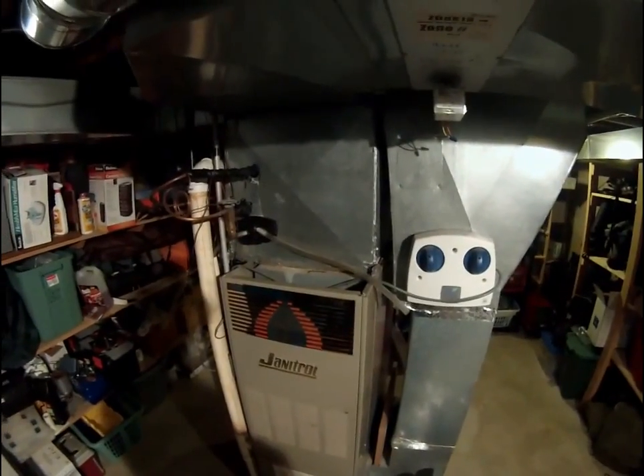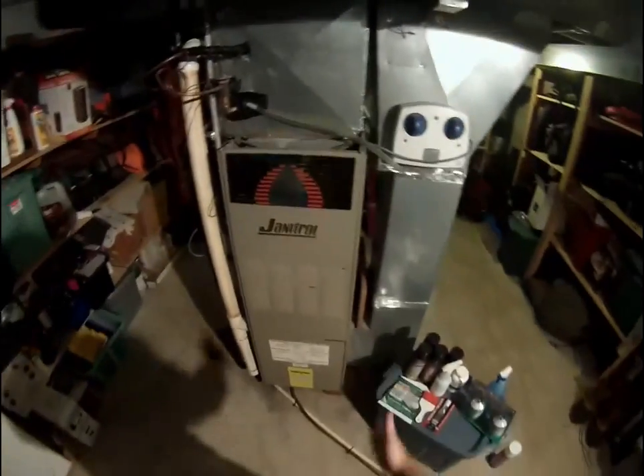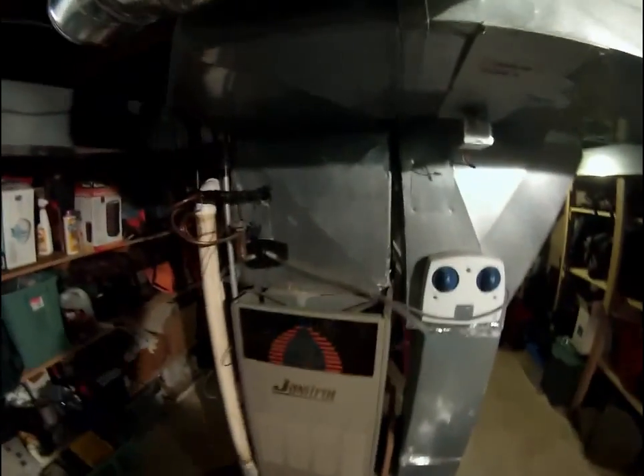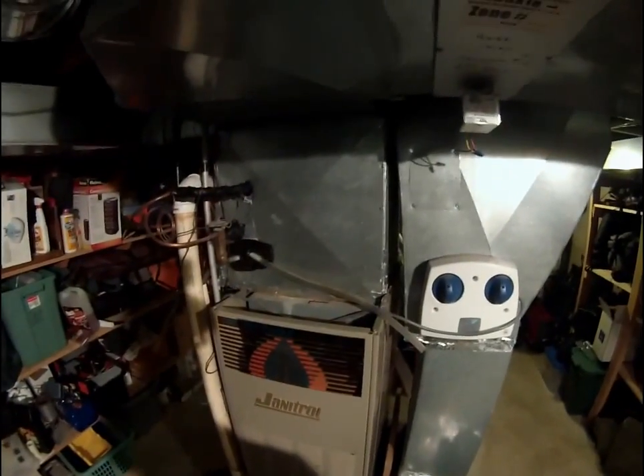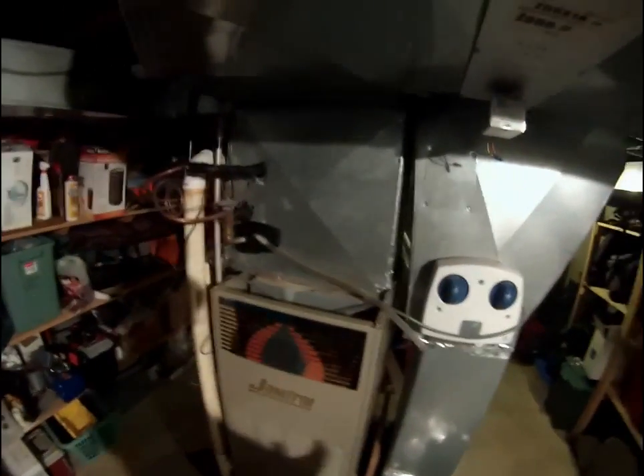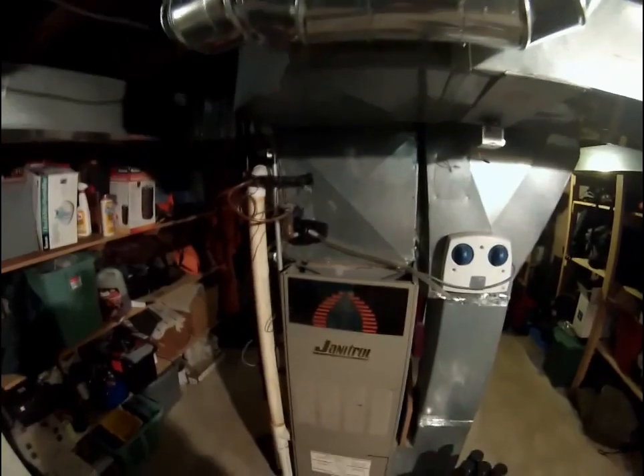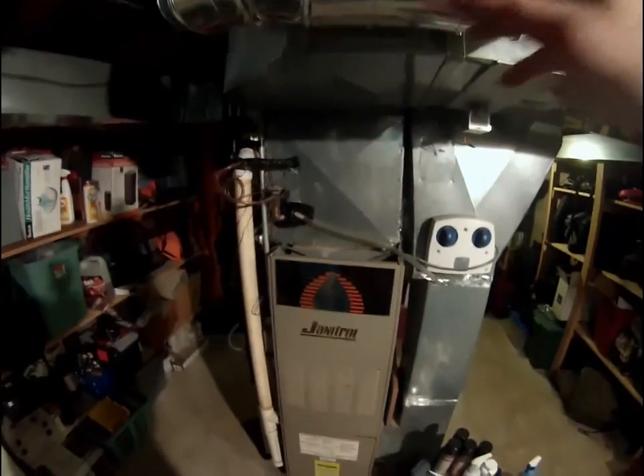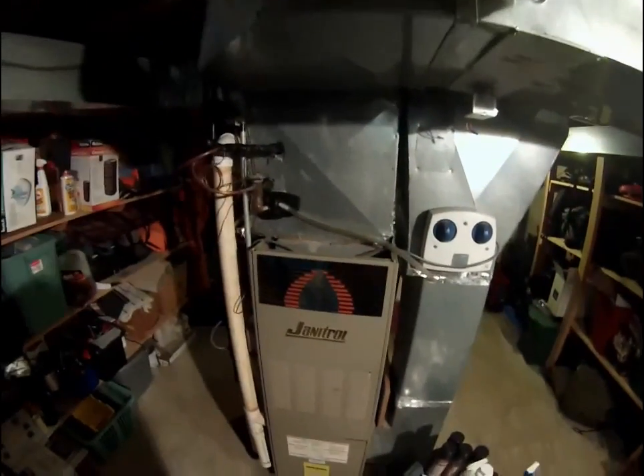Again, typically an air conditioner freezing up is related to either an airflow problem or a low on Freon problem. To a point, when it starts losing Freon, it'll freeze up. After it loses so much, it won't even freeze up anymore, it just won't cool. You also notice reduced airflow and obviously no cooling upstairs at your register.